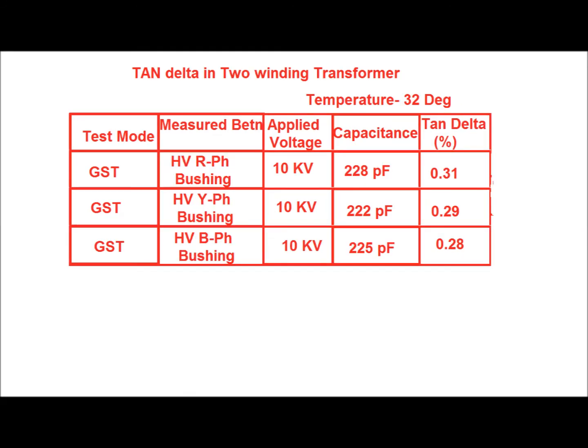Bushing tan delta is measured in GST mode for HV red phase, Y phase, and B phase bushing. Tan delta values are 0.31%, 0.29%, and 0.28% respectively, and capacitance values are 228 picofarads, 222 picofarads, and 225 picofarads respectively. The applied voltage is 10 kV and temperature is 32 degrees.